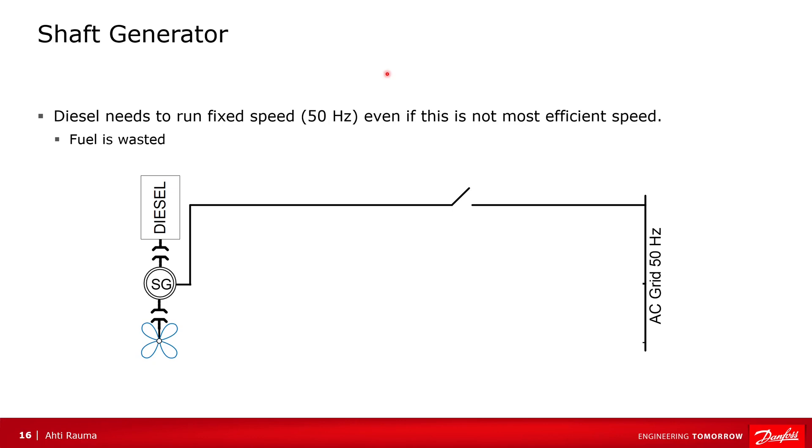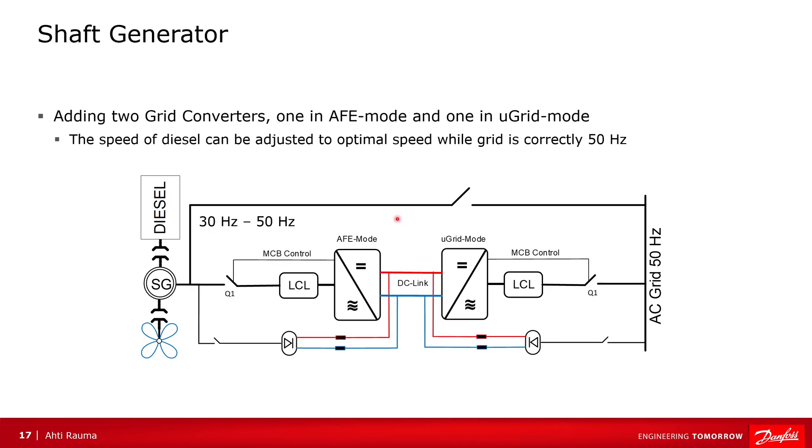Shaft generator use case. On many ships there is a propulsion and shaft generator on the same shaft. This means the diesel needs to run at a certain fixed speed so that the grid has the correct frequency. This fixed speed means the pitch angle may not be optimal for the required ship speed, and fuel is consumed for the engine speed rather than toward ship speed. If we add active front-end and microgrid mode drives, we can change the diesel speed. The active front-end can still make the DC link for the microgrid mode, and the microgrid makes the 50 Hz grid while the diesel speed is completely different — allowing the diesel speed to be adjusted for optimal fuel consumption.